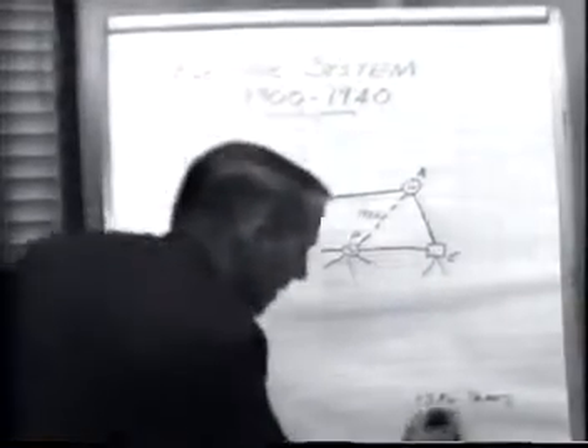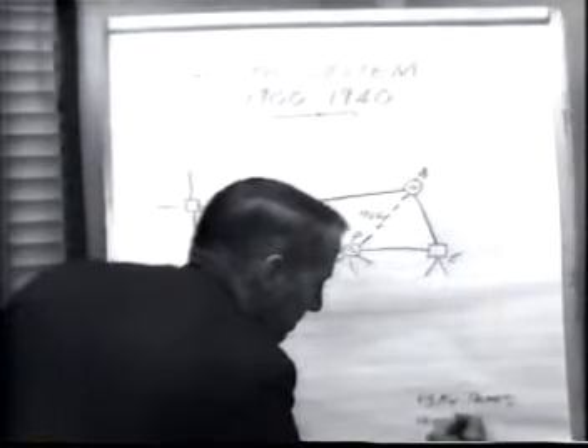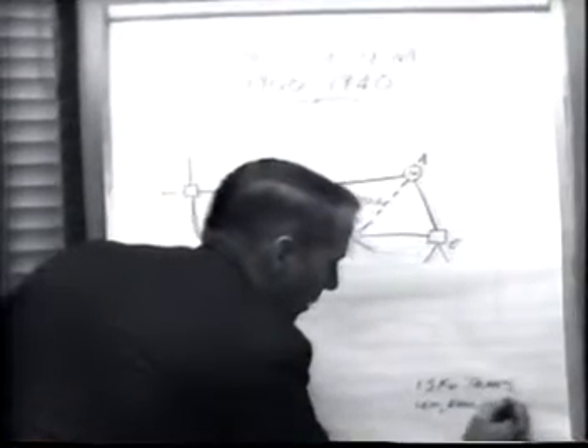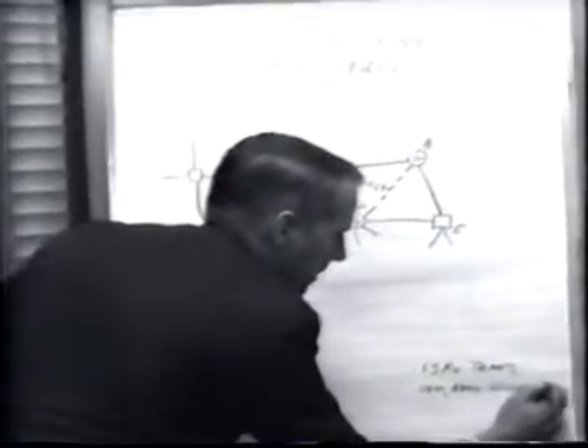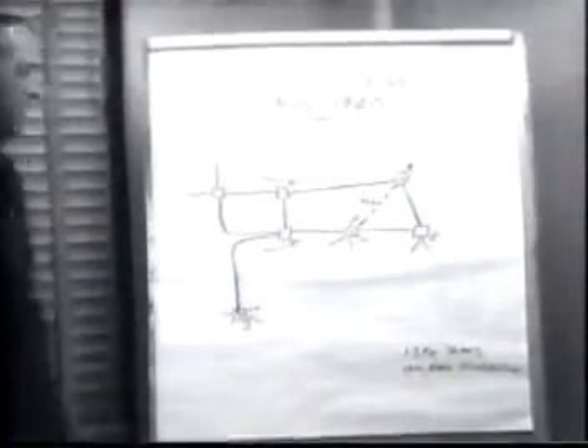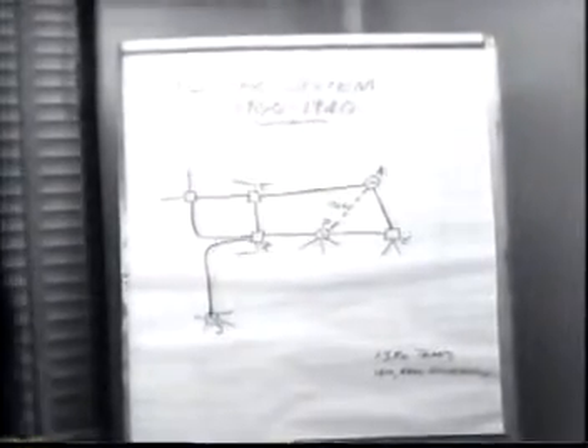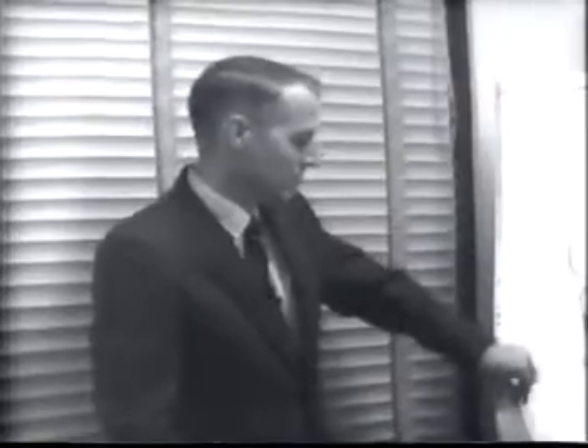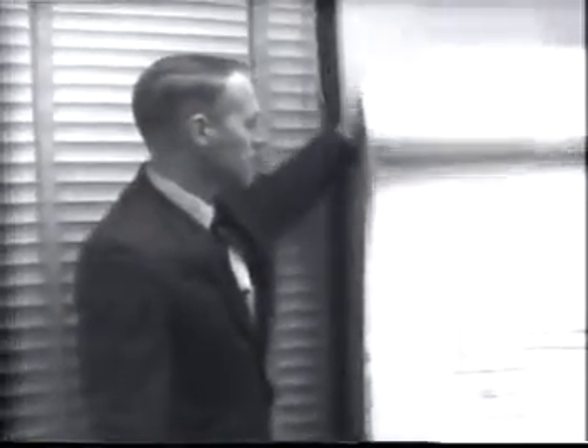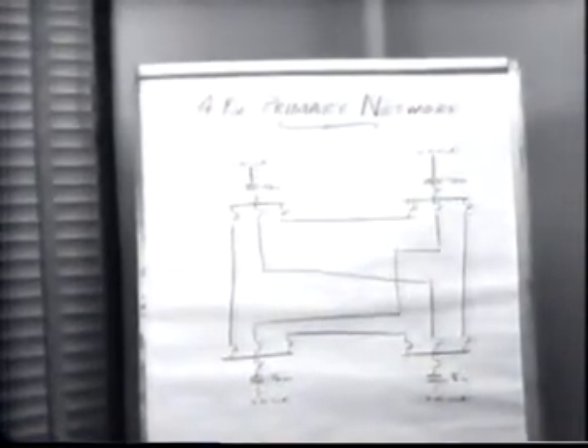This system with 13 kV transmission lines with a 69 kV backbone line between Riverside and Moline plant, and with 2400 volt and 4800 volt distribution, works surprisingly well up into the middle and later 30s. In the later 30s, we started in on and developed a new type of primary distribution system to provide greater reliability of electric service in this area. It's called a 4 kV primary network system. This is a typical or general description of the distribution system.